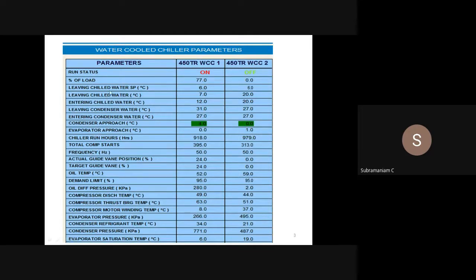For example, you will know what is my percentage load on this chiller. It is a 450 ton helical rotary screw chiller. 77% it is running. Leaving chilled water set point is 6 degrees. Leaving chilled water is 7 degrees, which means, since it is loaded only 77%, it is still 7. Maybe in another 10-15 minutes, I may get 6 degrees centigrade. What is my entering temperature? 12 degrees. Leaving condenser water 31. Entering 27. Condenser approach is 4 degrees centigrade.